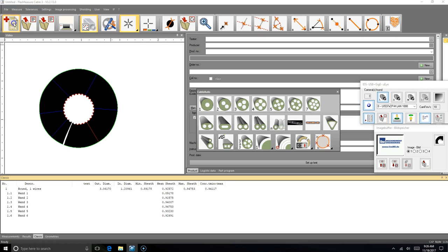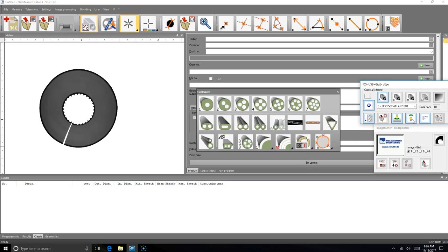So I'm going to go ahead and get rid of this. I'm not going to save this test plan. You could, and I'll show you that later. But in this case, this one might have 3 layers. To see that, I'm turning on this backlight icon. This is the front light icon, and that's the backlight icon. This is one of the other 2 things you might do if you need to measure multiple layers. Now I turn on the backlight, and you can see it has 1 layer here, another layer, and another layer. So still some single conductor, still got a slit in it, and now we're going to show that it has 3 layers. Okay, and then we're going to push go.